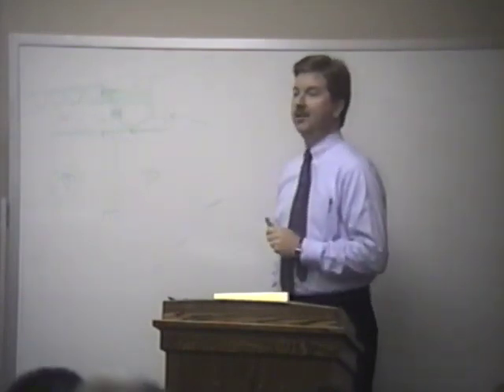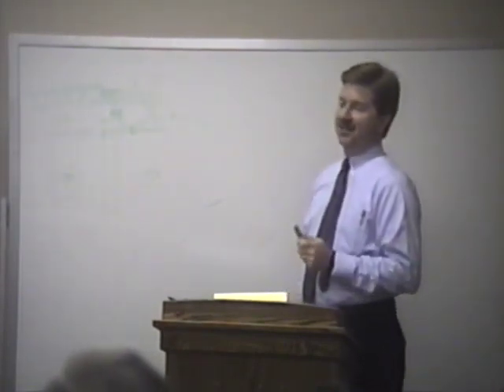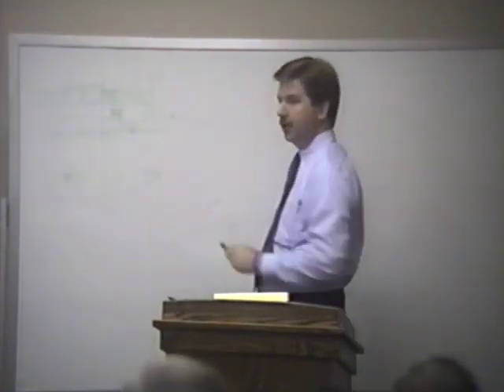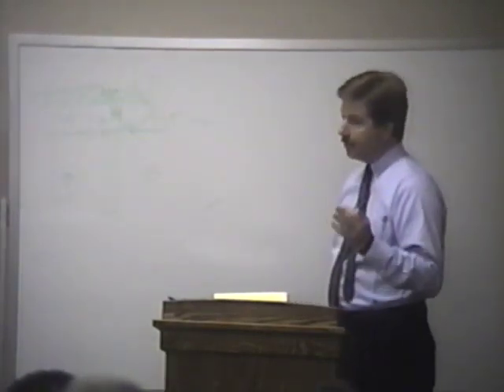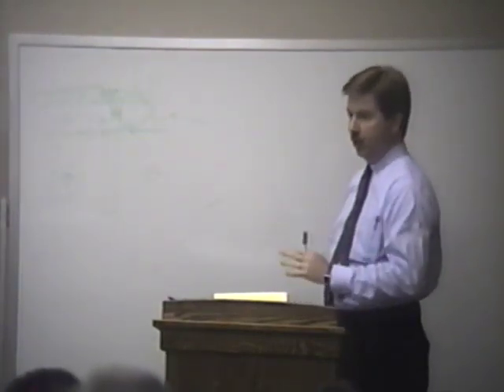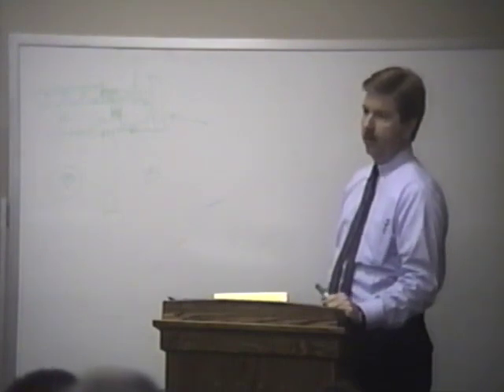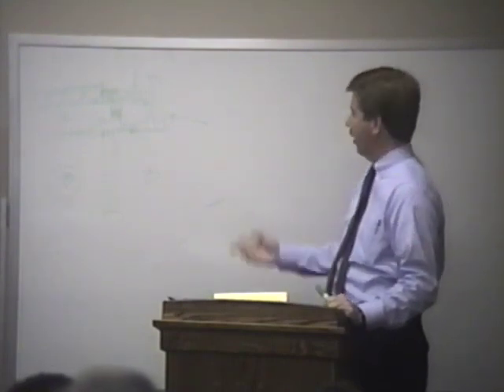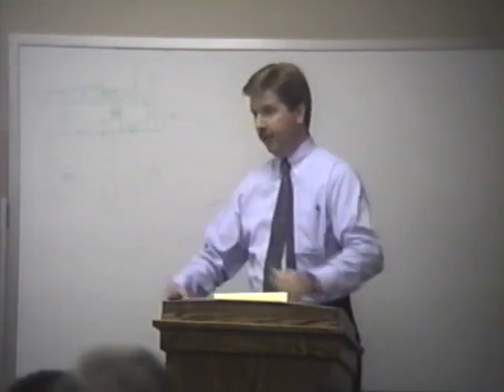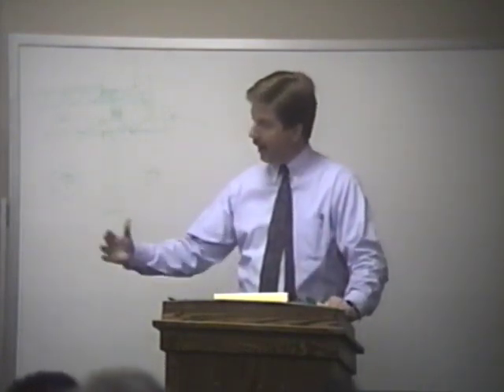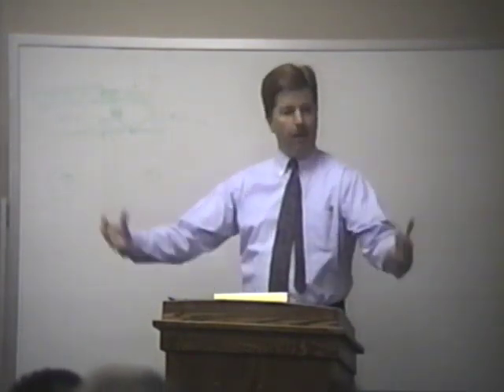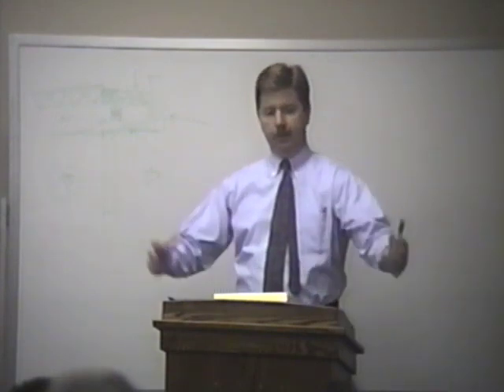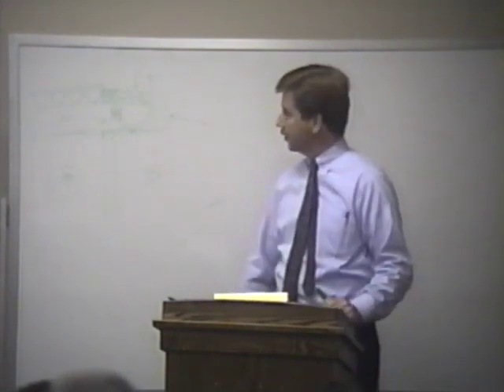Well, I came to the conclusion it was obviously gross negligence on the engineer's fault. Whenever he saw it was this bad, he should have said, hey guys, we need to change something. You really want me to put unit heaters up there? For the record, if we have a problem with this, I'll have to state I had to put unit heaters in your plenum because it's so bad at design. Somebody was not communicating. I don't know who to blame, but you can't believe this actually happened.